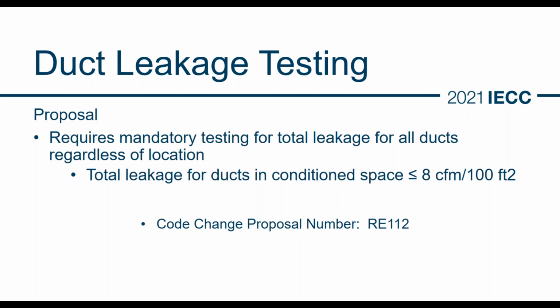The U.S. Department of Energy has conducted several residential energy code compliance studies over the years. As part of that study, they decided to test all ductwork regardless of whether it was in conditioned or unconditioned space. The thought behind not testing ducts in conditioned space was that if the ducts leak, they just leak into the conditioned space anyway, so it won't cause any issues. What they found is that a lot of ducts in conditioned spaces leak. I know we were involved in studies in Kentucky, and even though all the ducts were located in conditioned space, they could barely pass the test because the ducts were so leaky.